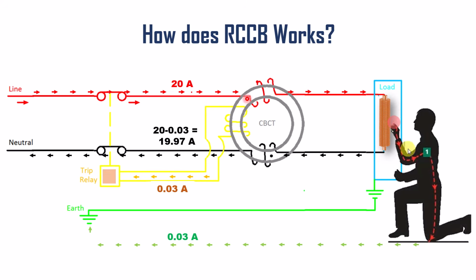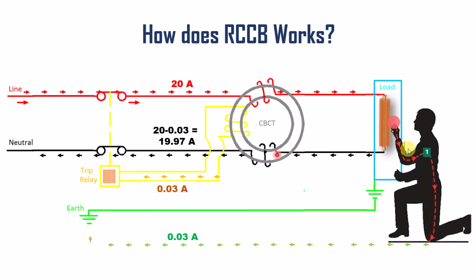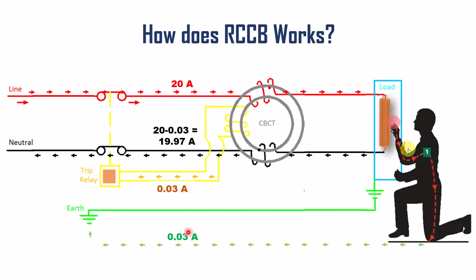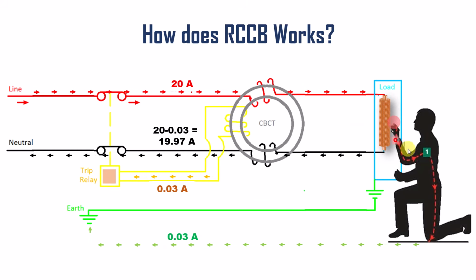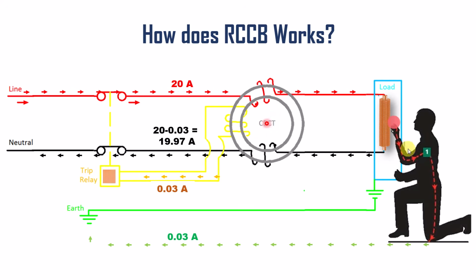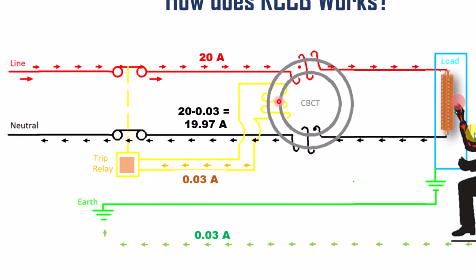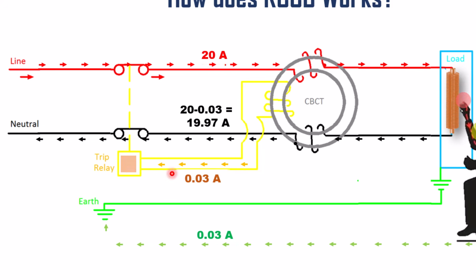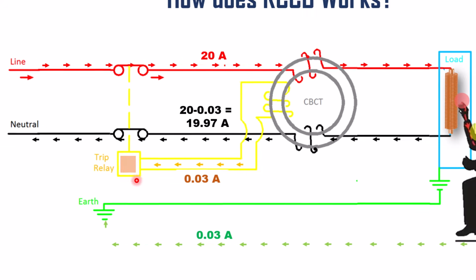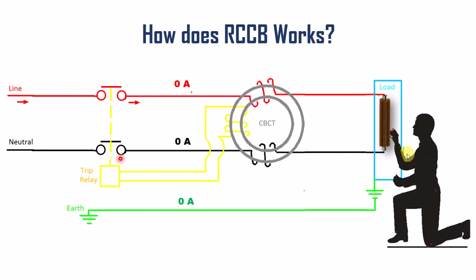Here you can see the phase conductor is carrying 20 ampere, whereas the neutral conductor is now carrying 19.97 ampere, because 0.03 ampere is flowing through the human body into the earth. So the resultant of both the currents, which is 0.03 ampere, now starts to flow in the secondary of this coil, which energizes the trip circuit, and as a result it opens the contact and trips the circuit and protects the human from electric shock.